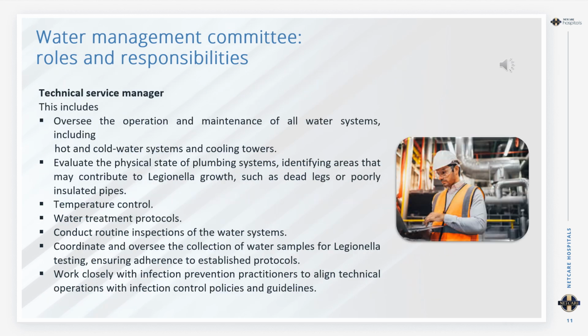The technical service manager should also be part of this committee. They oversee the operation and maintenance of all water systems, including hot and cold water systems and cooling towers. They evaluate the physical state of plumbing systems, identifying areas that may contribute to Legionella growth, such as dead legs or poorly insulated pipes. Temperature control, water treatment protocols, for example, with chlorine. Conduct routine inspections of the water systems. They coordinate and oversee the collection of water samples for Legionella testing, ensuring adherence to established protocols, and they work closely with infection prevention practitioners to align technical operations with IPC principles.